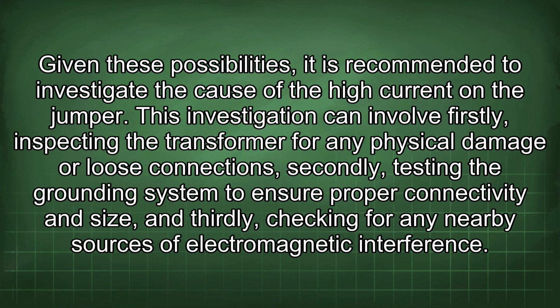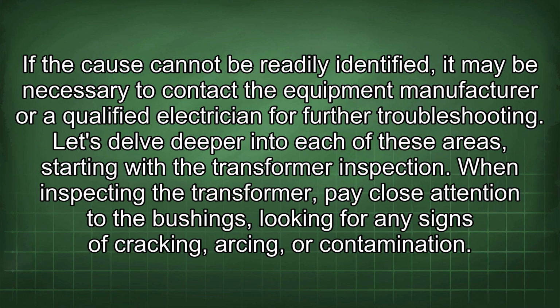Given these possibilities, it is recommended to investigate the cause of the high current on the jumper. This investigation can involve, firstly, inspecting the transformer for any physical damage or loose connections, secondly, testing the grounding system to ensure proper connectivity and size, and thirdly, checking for any nearby sources of electromagnetic interference. If the cause cannot be readily identified, it may be necessary to contact the equipment manufacturer or a qualified electrician for further troubleshooting. Let's delve deeper into each of these areas, starting with the transformer inspection.